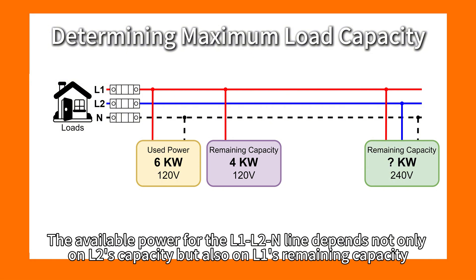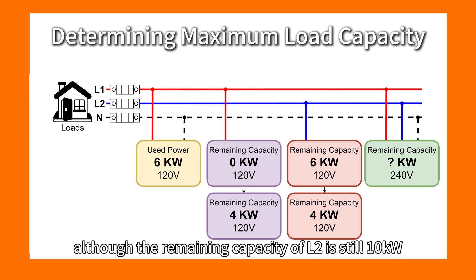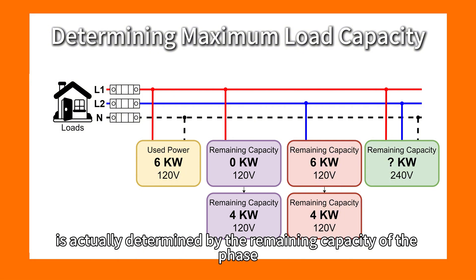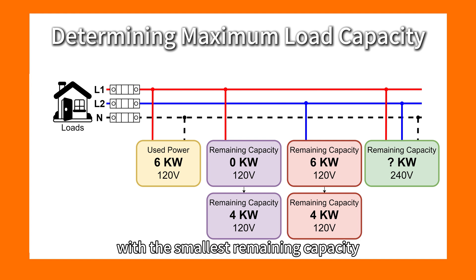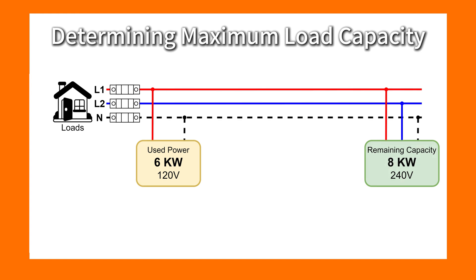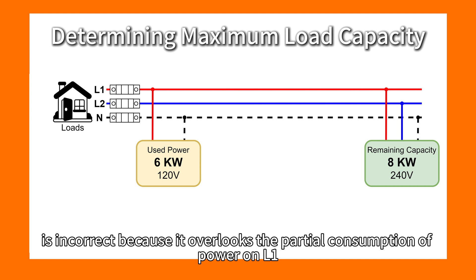The available power for the L1-L2 line depends not only on L2's capacity but also on L1's remaining capacity. Although the remaining capacity of L2 is still 10kW, the maximum supported power of the L1-L2 line is determined by the remaining capacity of the phase with the smallest remaining capacity. Since L1 only has 4kW left, the maximum power for the L1-L2 line is 4kW multiplied by 2, equaling 8kW. Simply subtracting the 6kW load from the total power limit is incorrect because it overlooks the partial consumption of power on L1.